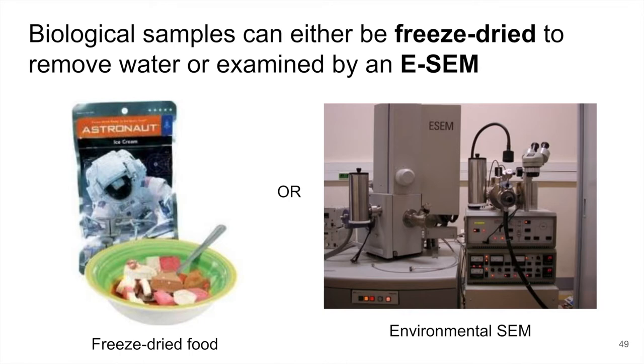Let's talk about some specialized applications of the SEM. We just talked about why we need a high level of vacuum in the SEM chamber, and this creates problems. If we want to look at biological samples, putting them in a vacuum takes them out of their natural environment. These biological samples tend to have water, which creates gas in a vacuum. There are two different approaches we can take to examine them.